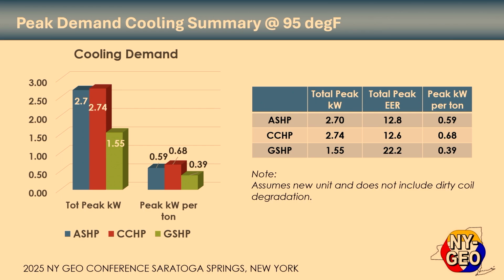Well, this is the cooling demand. I'm not sure which number you're wanting to take a look at. This is cooling, and this is at 95-degree outdoor air temperature. So our product would be running at a moderate, I think it's high 70s the way this is modeled here. So our loop temperature would be in the high 70s, but the air source heat pump would be working against 95 outdoor air temperature, which is typically how our loops would be sized.